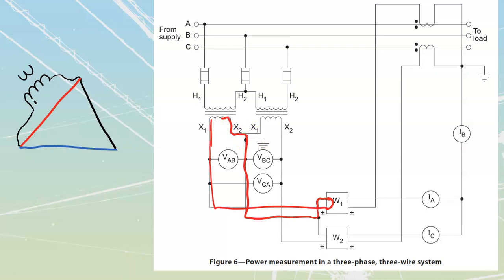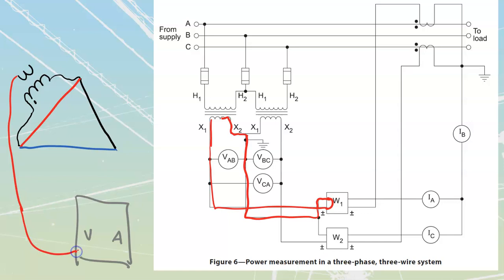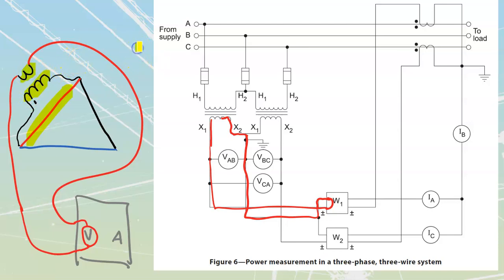So I'm going to do that down here. We'll draw out a larger watt meter once again. We'll call this volts, we'll call this amps, and I'll take my line from A here. This is going to be my line from A, and I'll bring that into my voltmeter section down here. It passes through the meter, then comes back out and goes back up, around to the outside, opposite side, like that. So whatever voltage is on this phase, we're going to transform that down from whatever value it is into no more than 120 volts using this system.